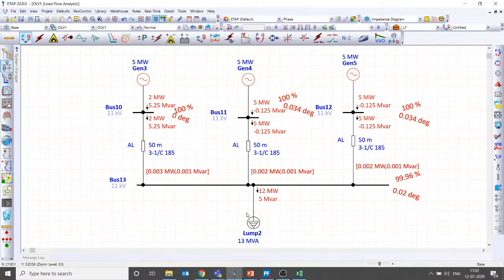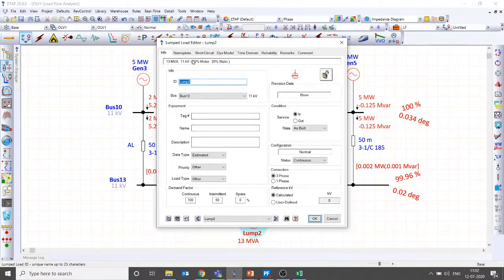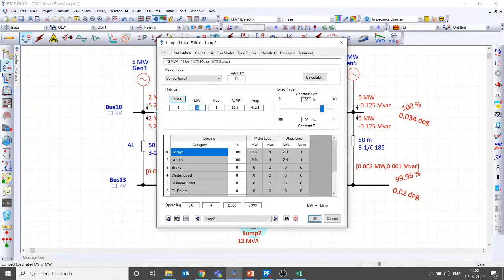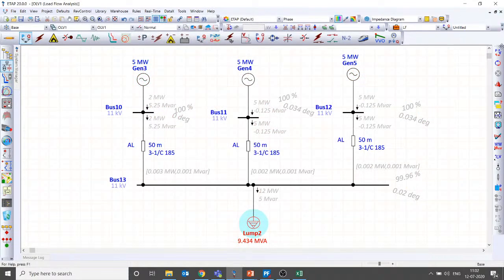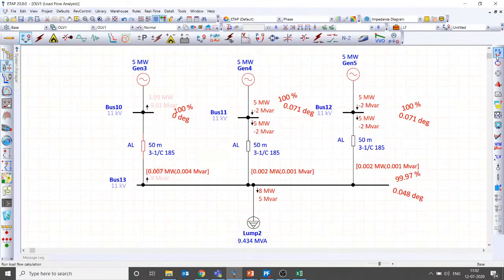And the scenario gets worse when your demand further reduces to, for example, 8 megawatt. When the demand is 8 megawatt, I'm not really worried about reactive power, I'm purely worrying about real power. If the load goes down to 8 megawatt with all three generators running, we expect each generator to share 8 by 3, that is about 2.7 megawatt. But here you see the results. Both the generators in PV mode generate 5 megawatt each, so the total generation is 10 megawatt.